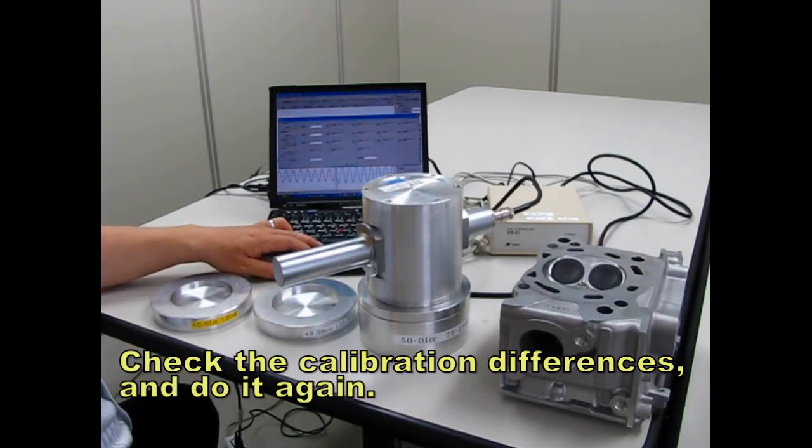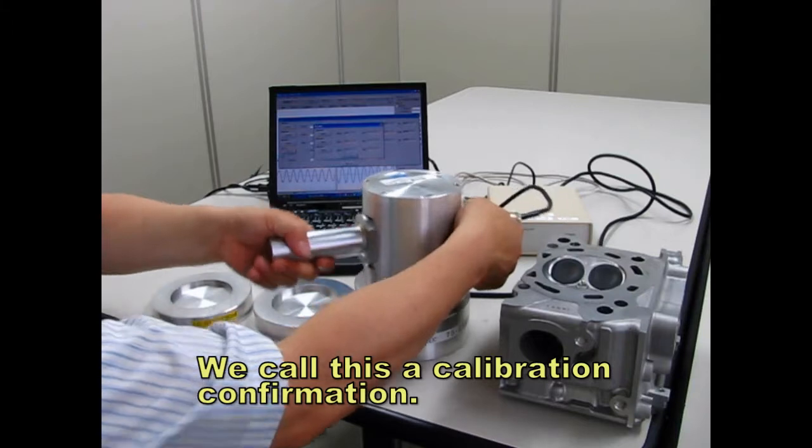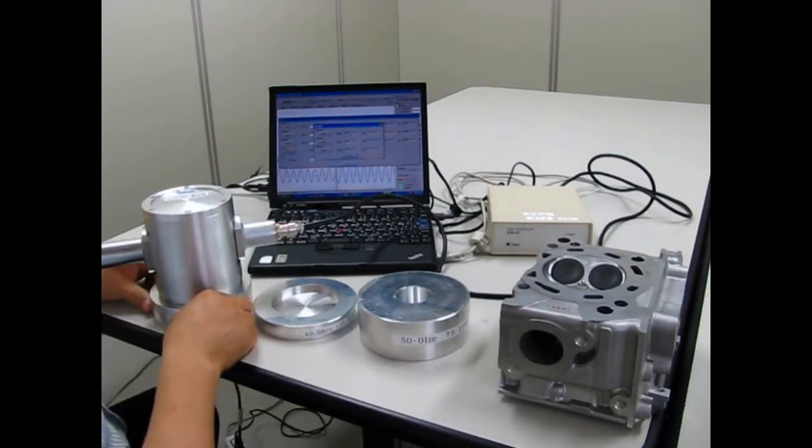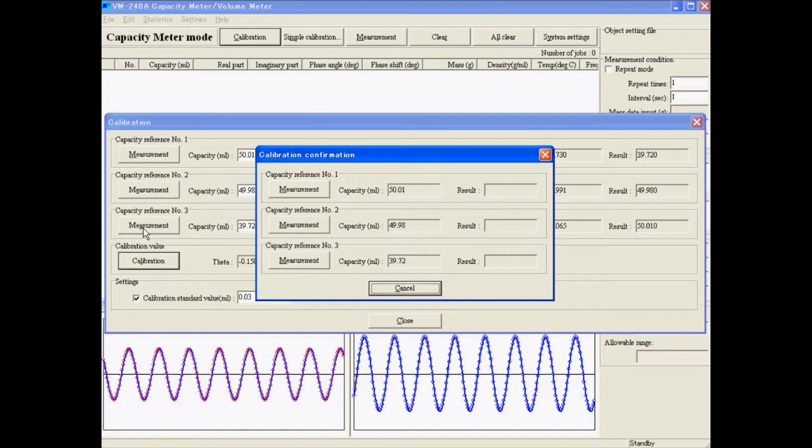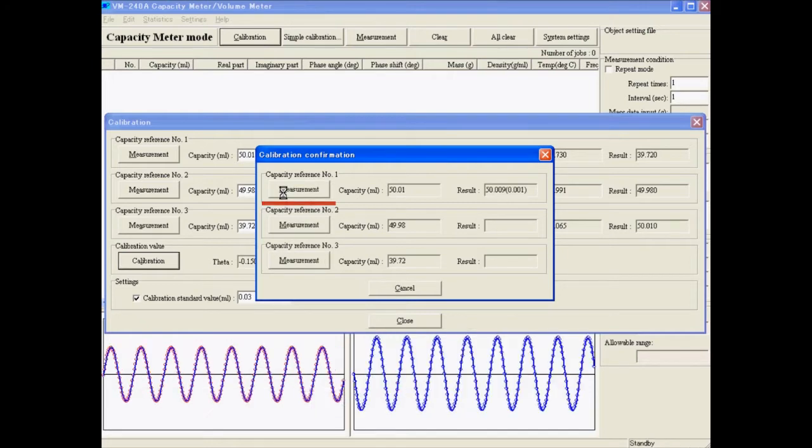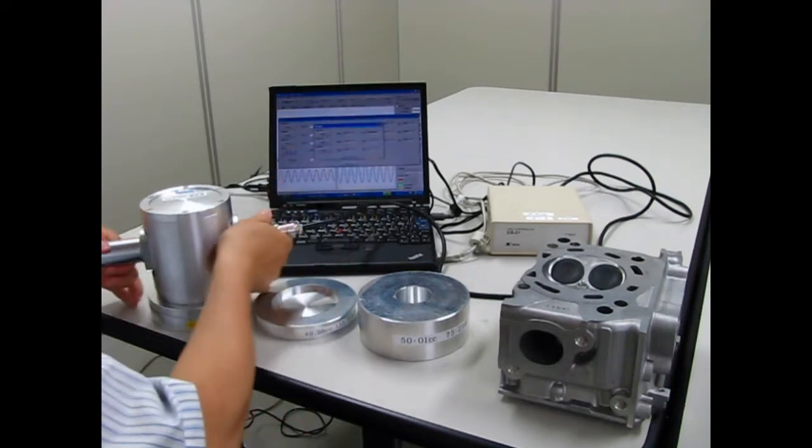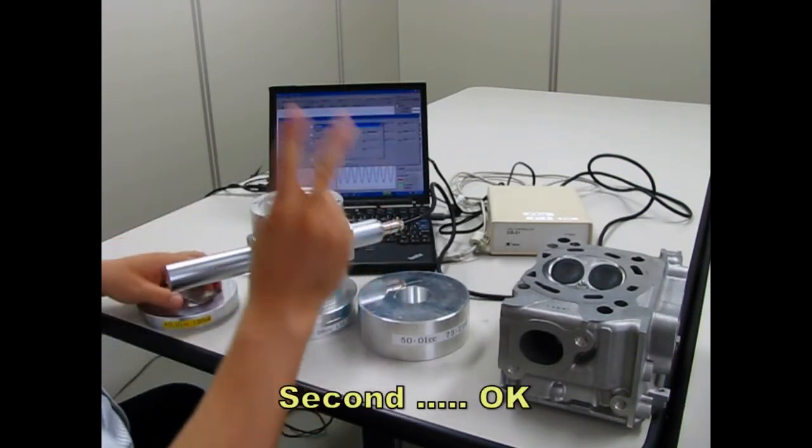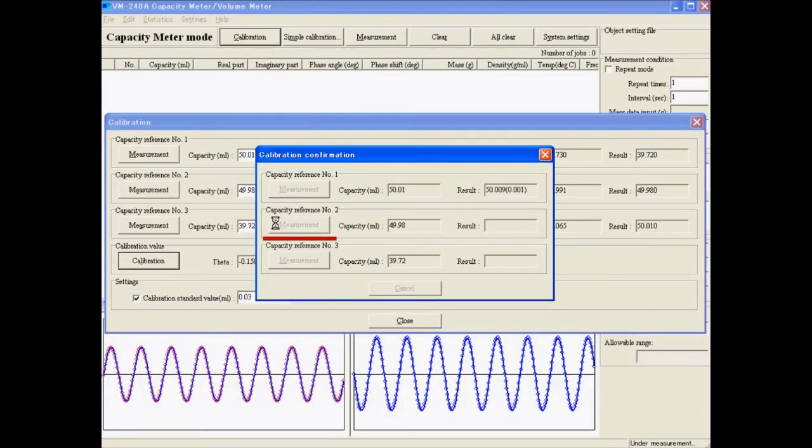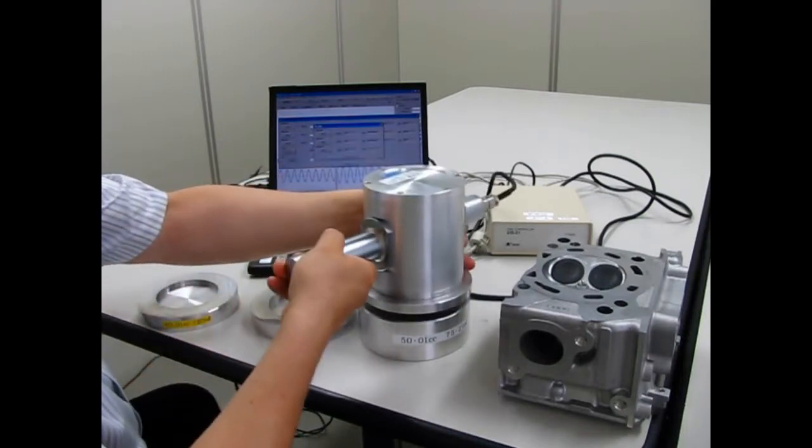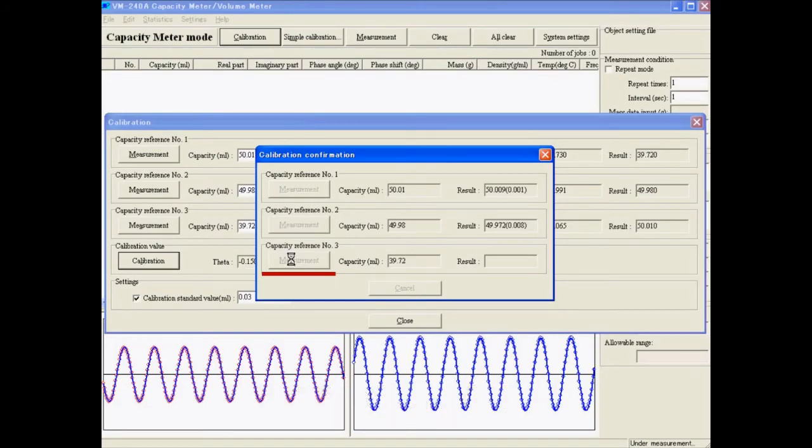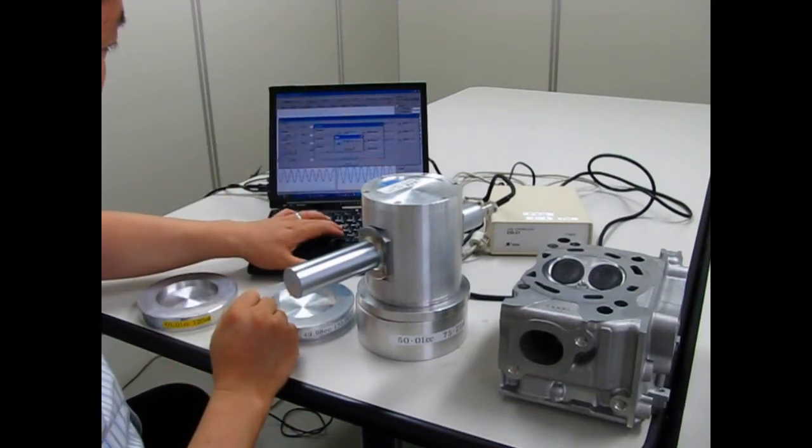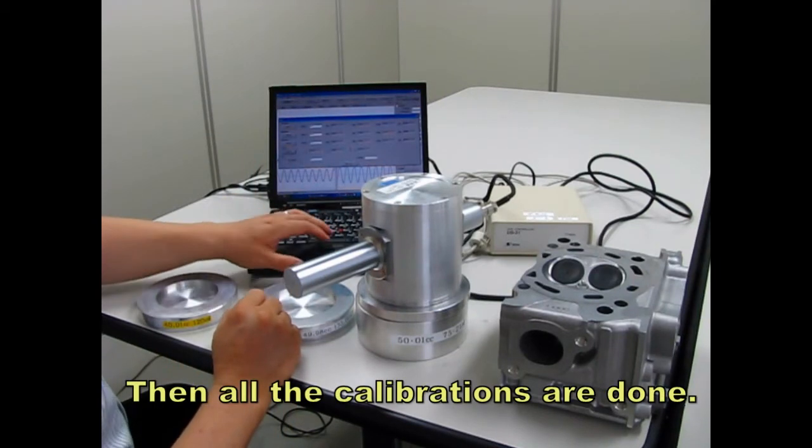Check the calibration differences and do it again. We call this a calibration confirmation. First, okay, second, okay, third, okay. Then all the calibrations are done.